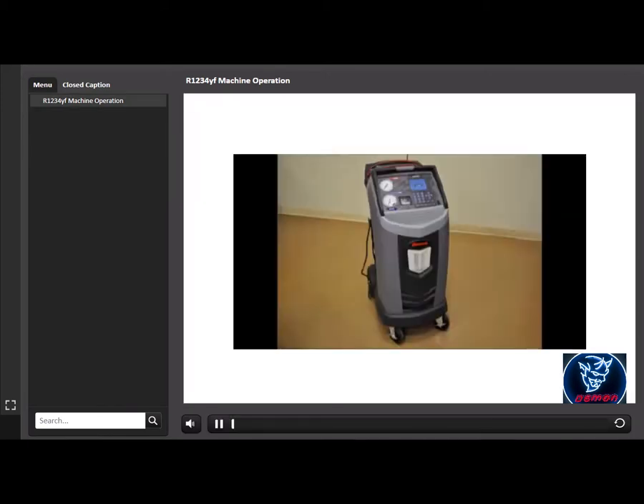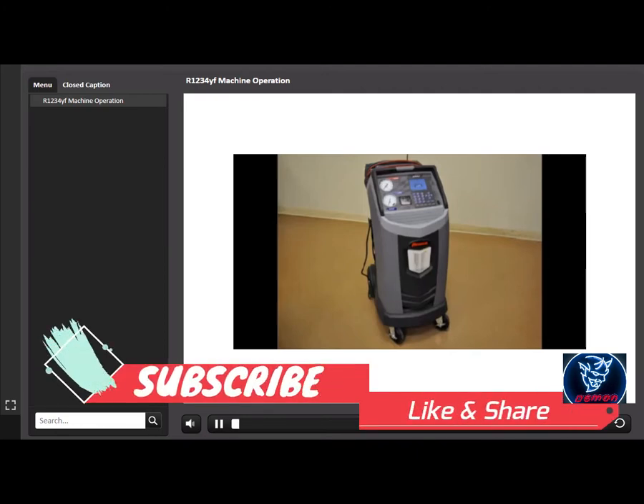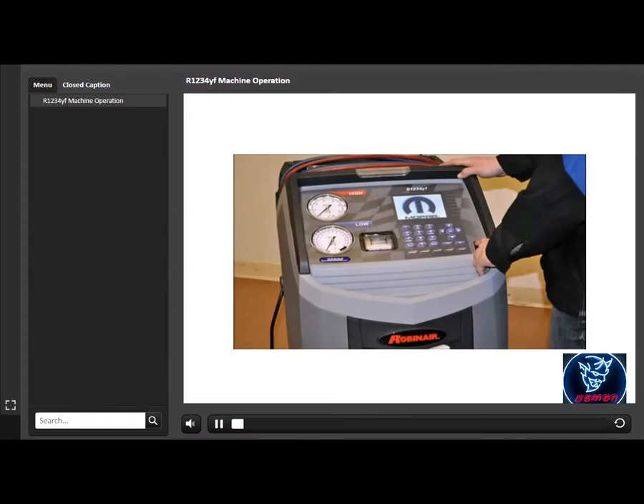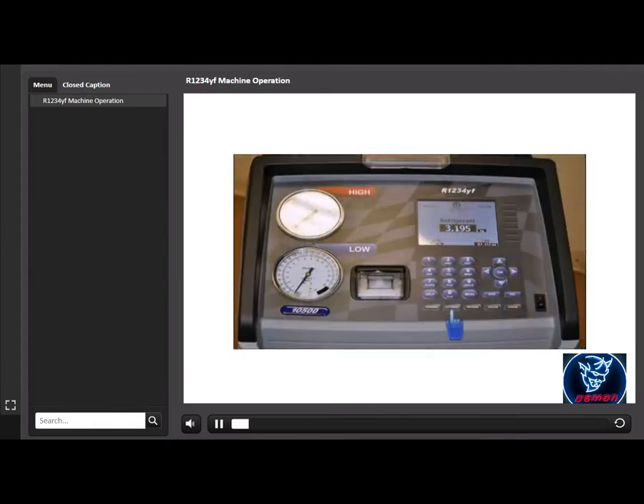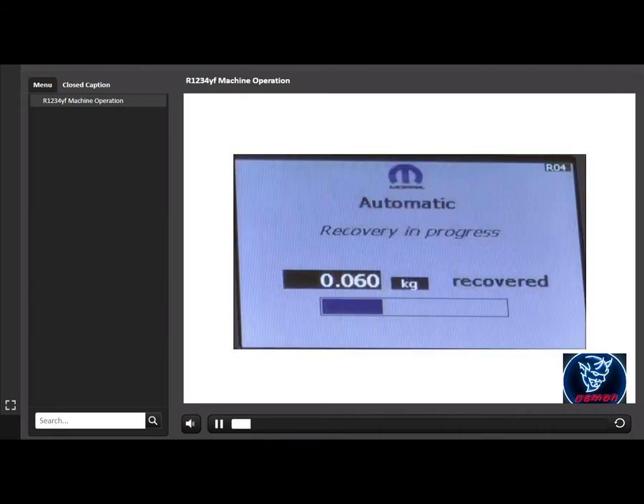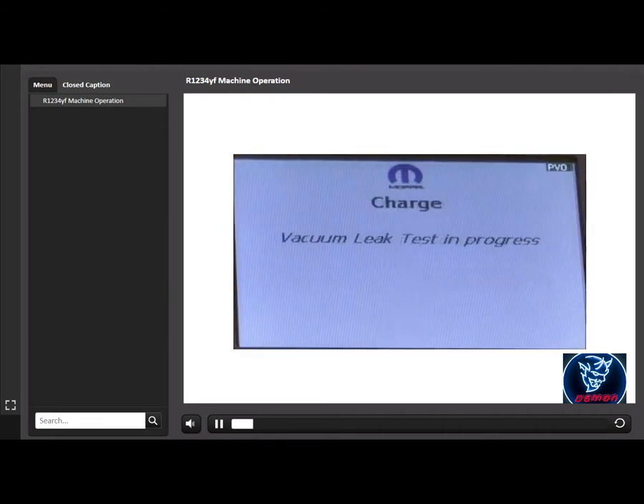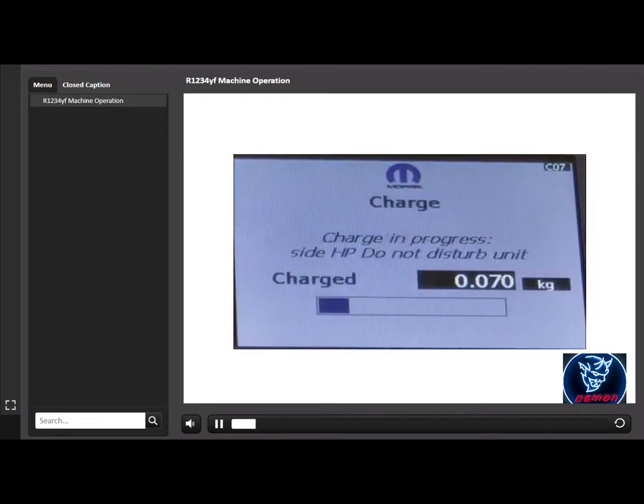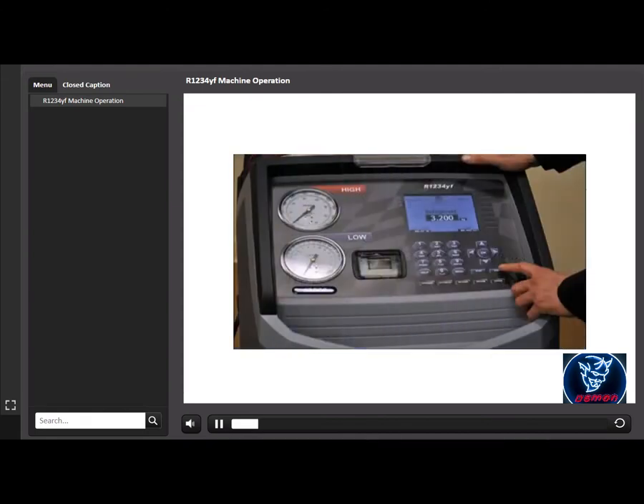The purpose of this Tech Tube release is to demonstrate the proper procedure to operate the new Robinair R1234yf refrigerant machine. With the machine plugged in, turn on the main power switch. The automatic function allows the user to program an automatic recovery, vacuum, leak test, and/or charge sequence. The user may choose to skip any step in the automatic operation during the programming. A total automatic sequence may take up to an hour.